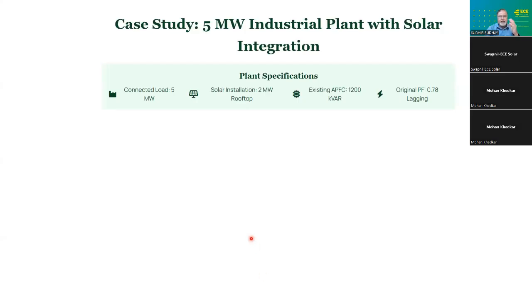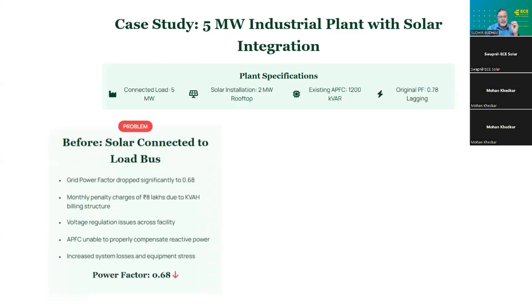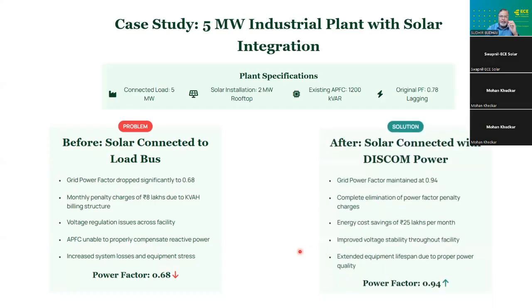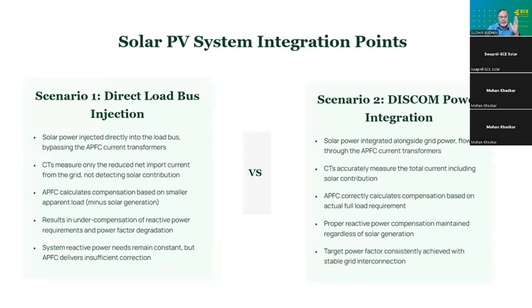So let's take a simple example of an industry with 5 megawatt connected load and 2 megawatt solar rooftop. Now there are two methods we can see. One is when the solar power is injected directly to the load bus, the LT bus. We have seen that in this case the power factor drops substantially, and it's not a good sign. But when you connect it along with the distribution panel, with the discom power, then the power factor remains almost at the level where they actually wanted to keep it. So the first scenario is direct injection into the load bus, and the second is along with the discom power.